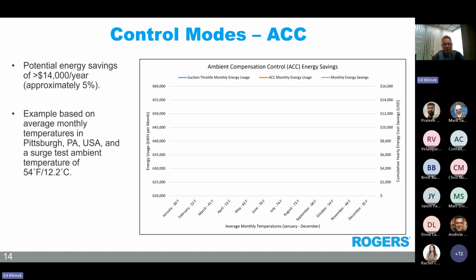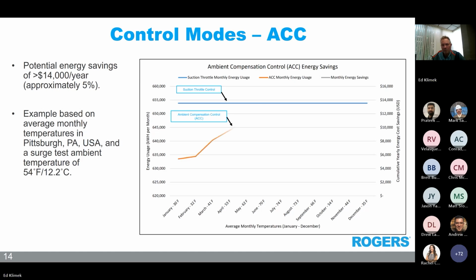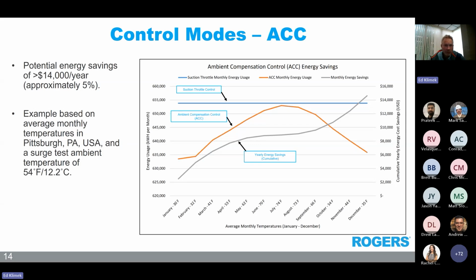I'm going to start the animation here. The first line shown will be blue and outlines the energy usage when operating in suction throttle control throughout the year. The second line is the orange line and outlines the energy usage when operating in ACC throughout the year. And the third line is the gray line and highlights the energy savings between suction throttle and ACC. It gives you the cumulative energy savings cost, which is between $14,000 and $16,000.